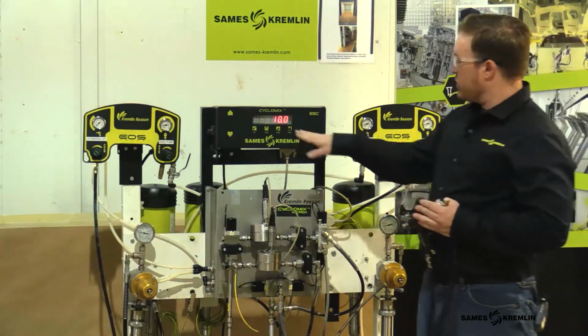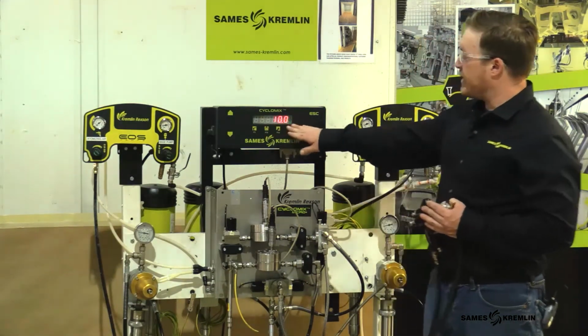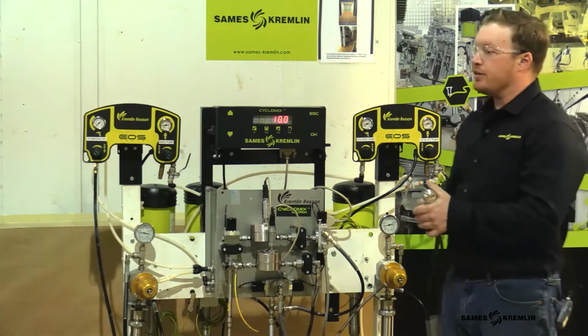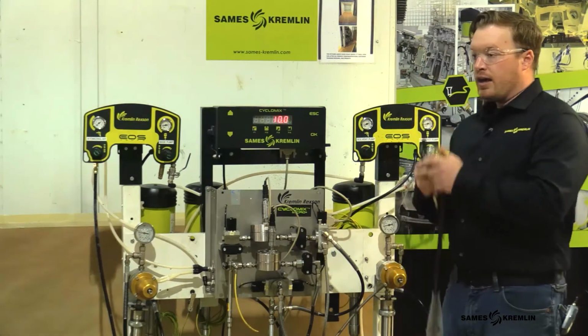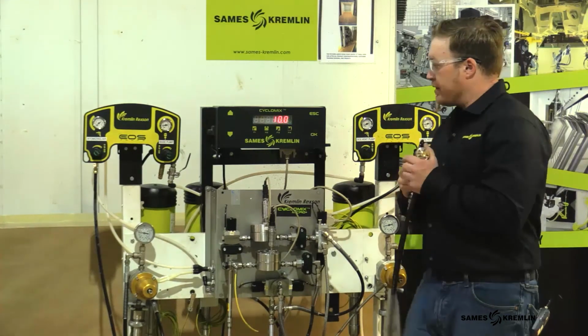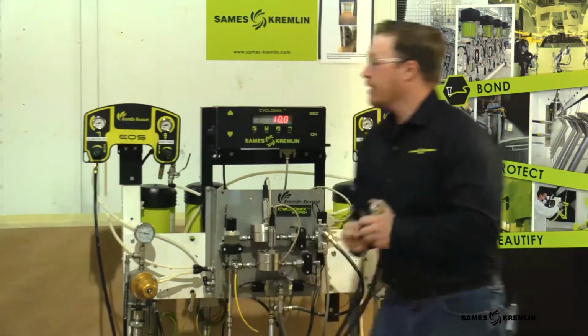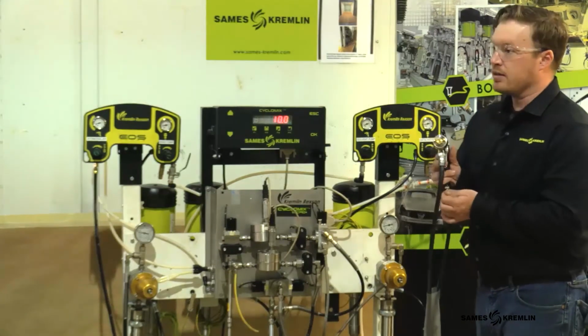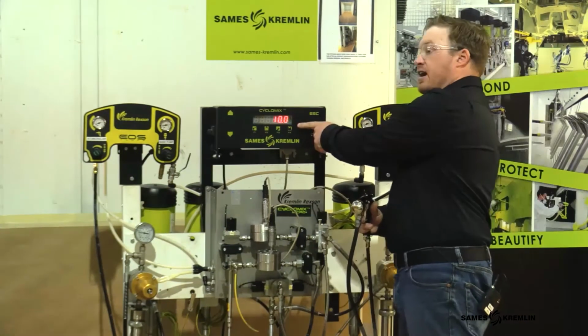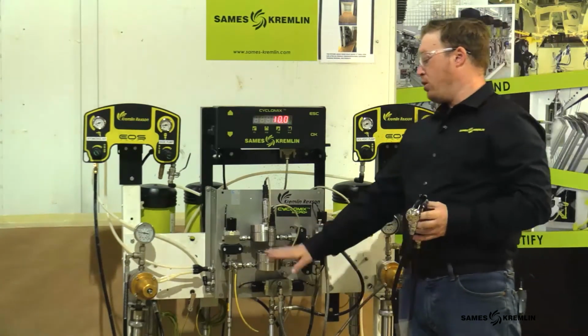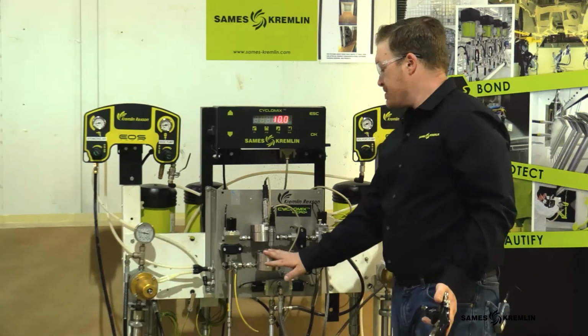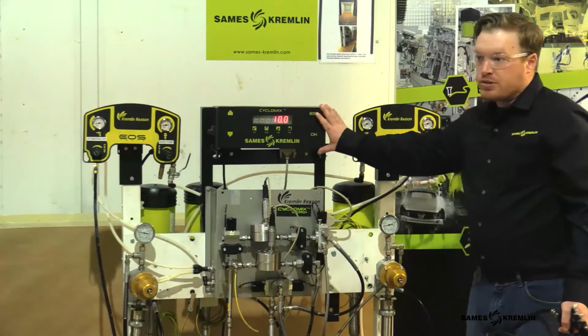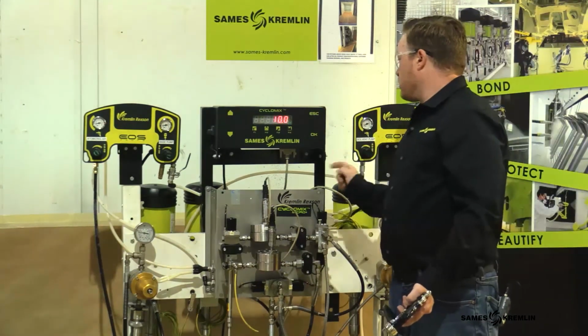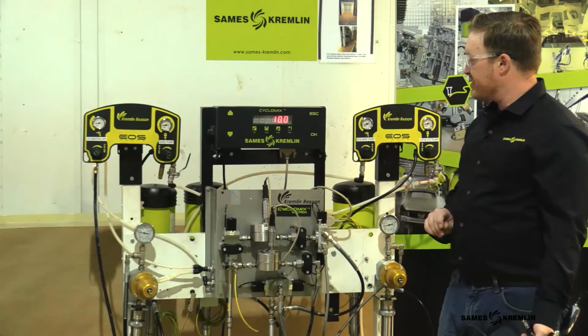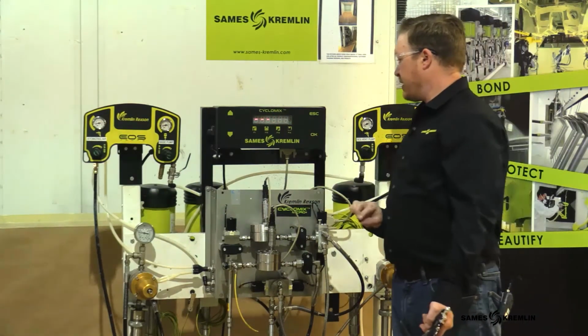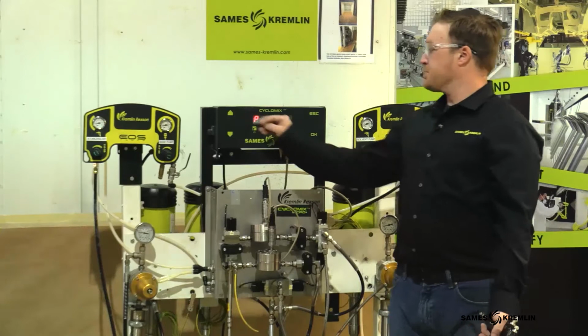So we're set up for 10 seconds here. This is in seconds. And what that is indicating is that your sprayers or your operators cannot have atomizing air on for a period of 10 seconds without seeing pulses from the A flow meter. It will air out. So we'll go ahead and leave that set up for 10 seconds right now. We'll validate that and move on to the next parameter.